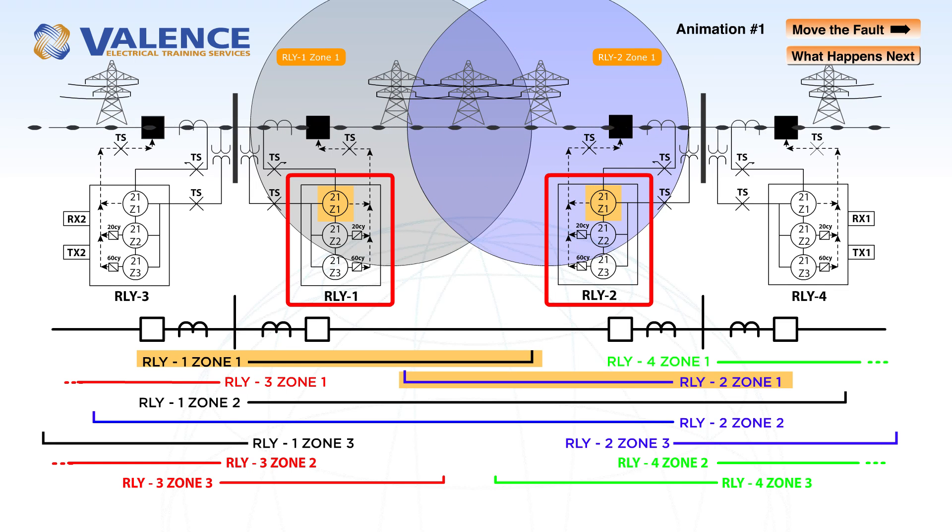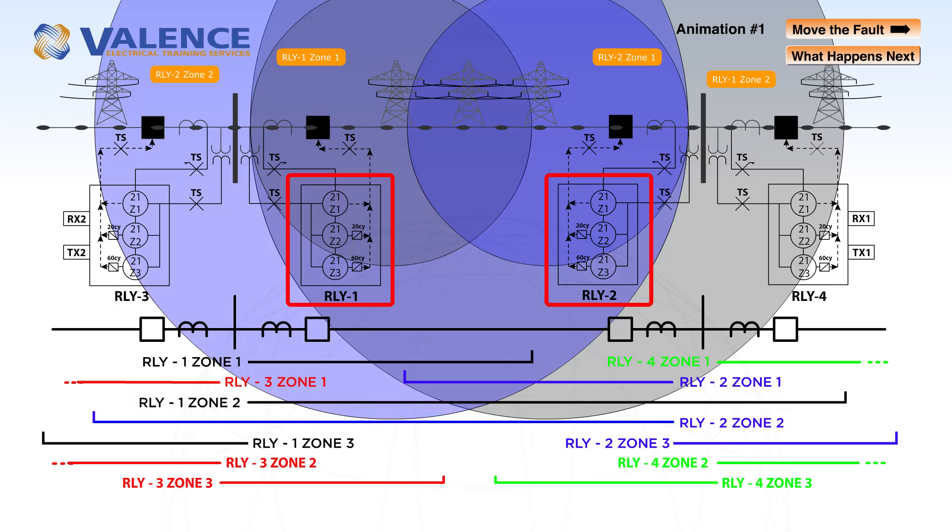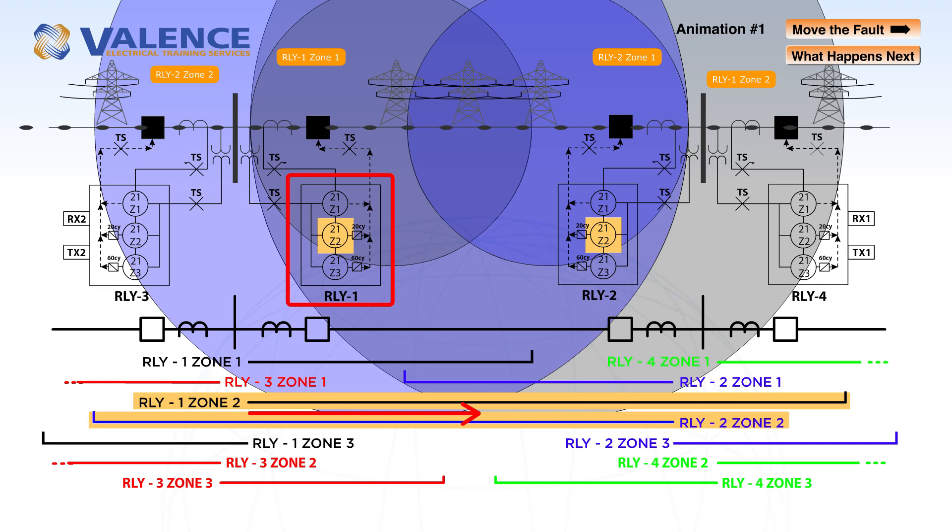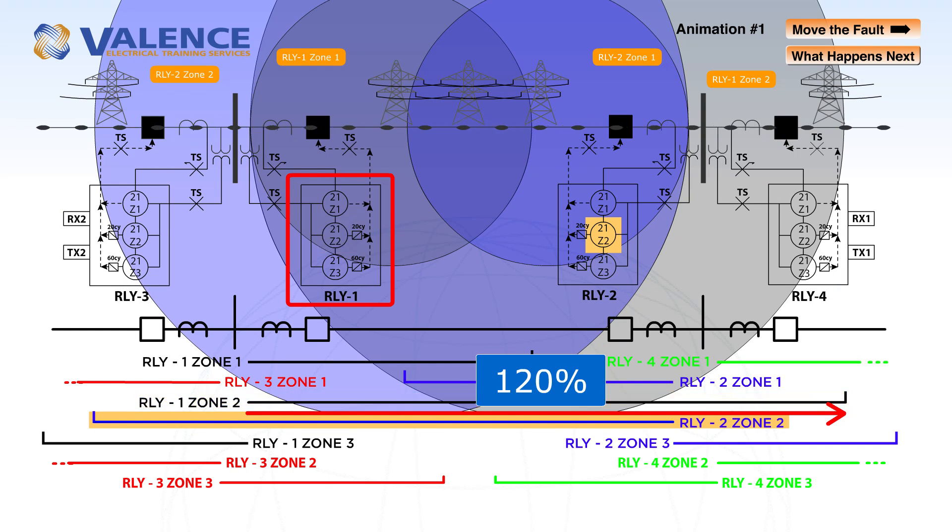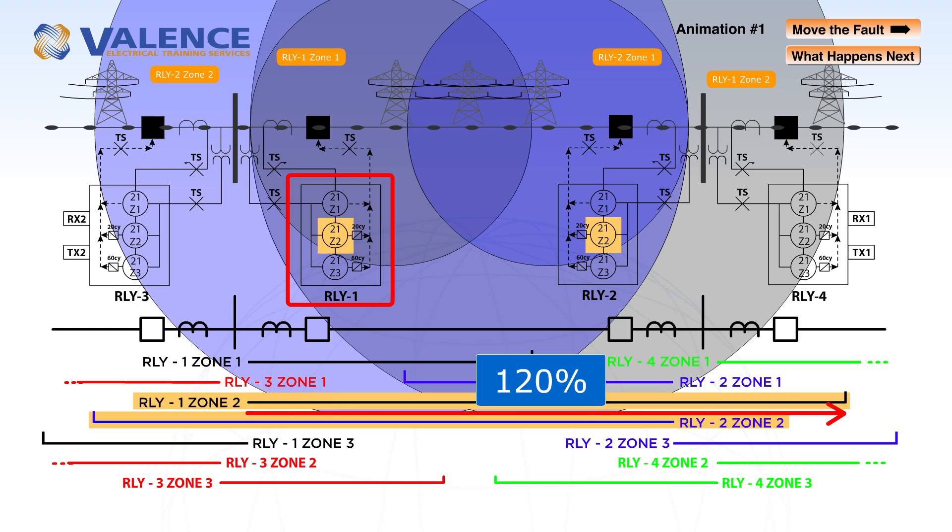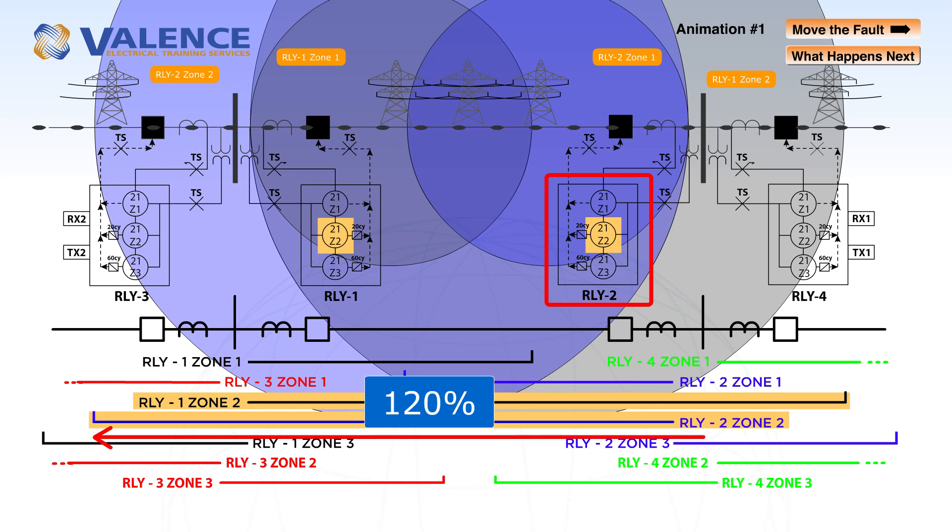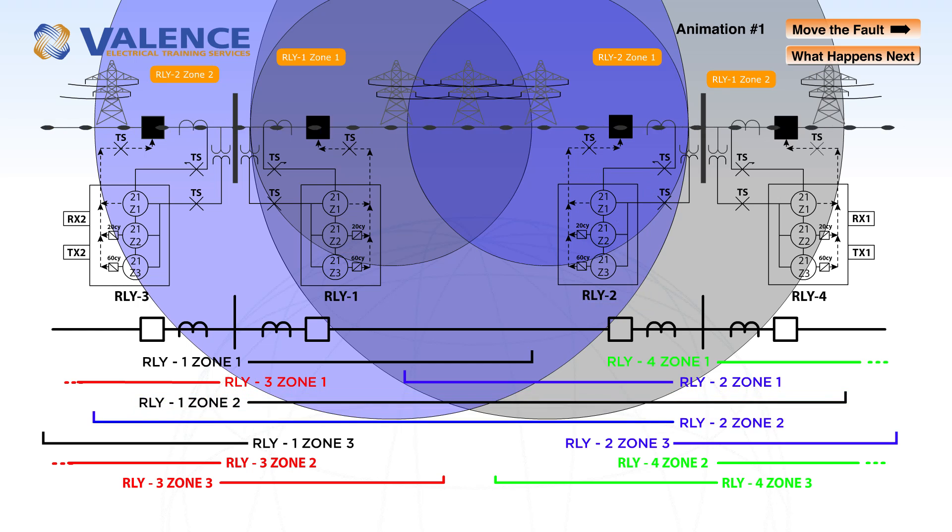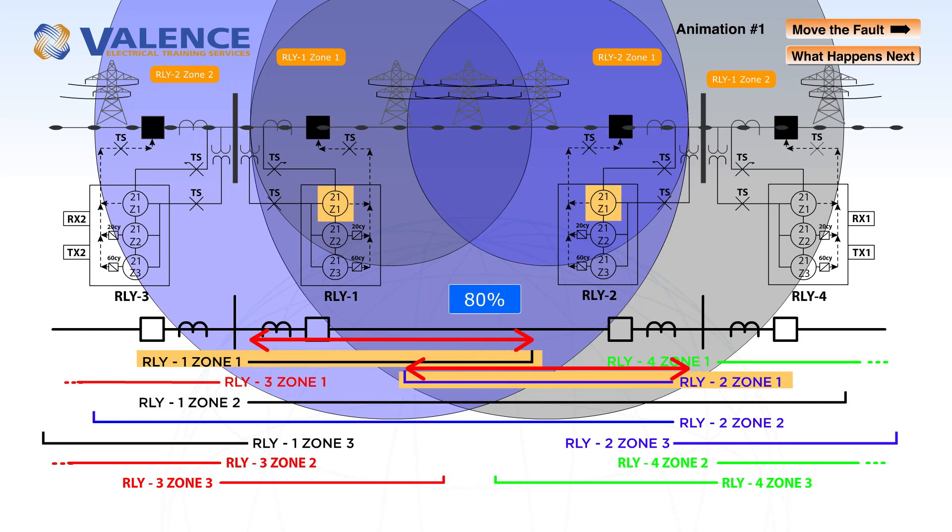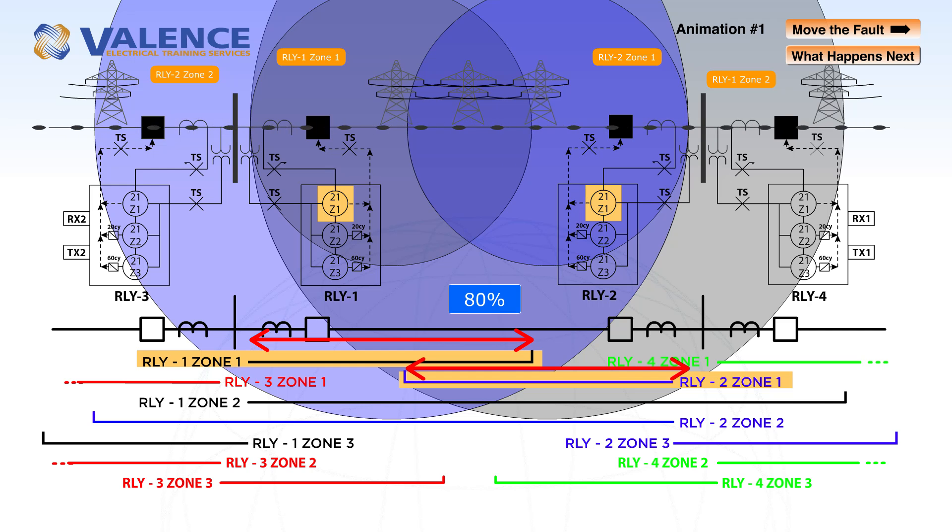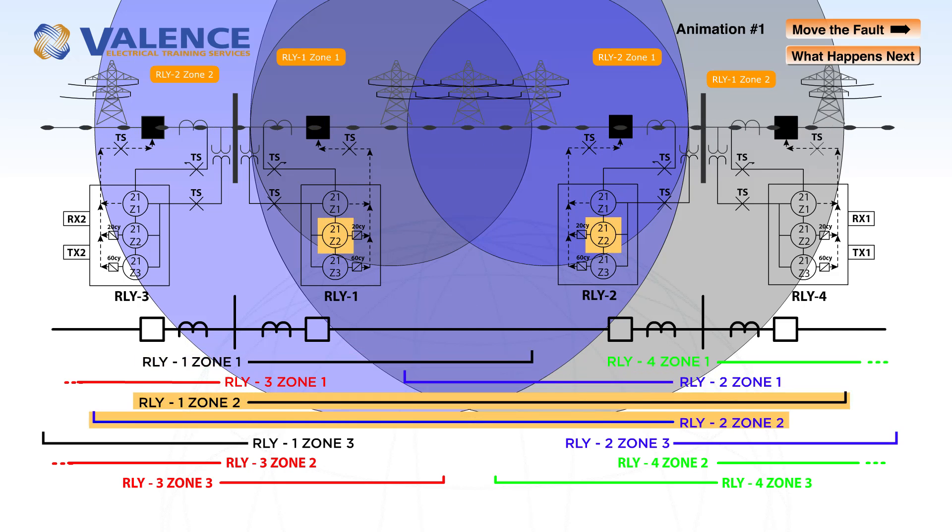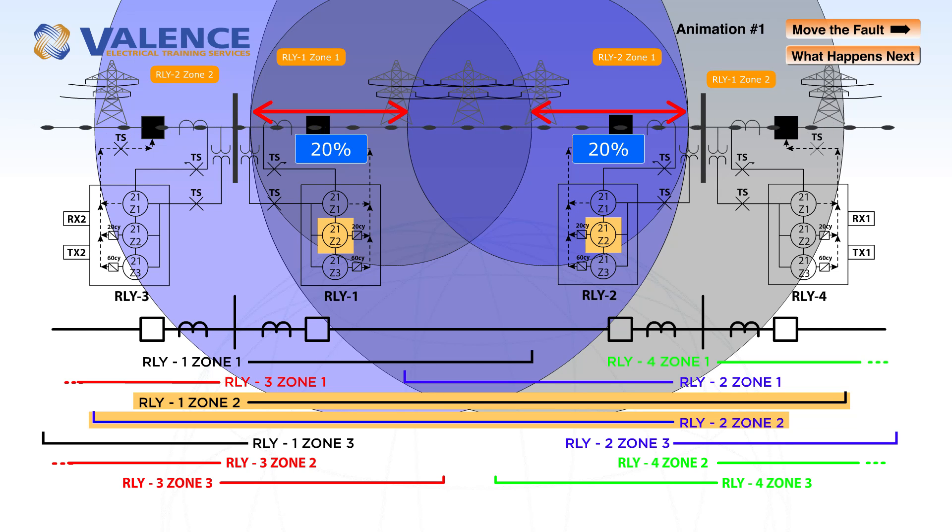Both relays also have zone 2 protection that reaches 120% down the line as shown by the zone 2 black line for relay 1 and this blue line for zone 2. As we discussed in the previous video, zone 1 is set at 80% of the line to compensate for any CT accuracy and calculation errors, and zone 2 will protect the other 20% of the line with a 20 cycle time delay.